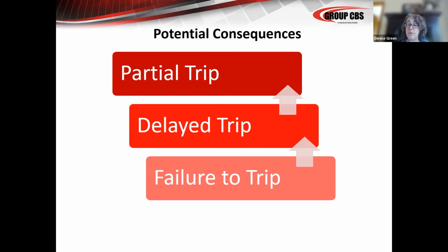What it turned out to be was, all the years that they were having the breakers tested, this was at a utility, so they never shut down the gear. Well, because of this event, the gear had to be shut down to be repaired. And when we got in the back and got the covers off, we found that a connection had not been crimped at time of installation. So all the years of spiking faults on that loose connection on the cable was causing the interrupters to fail. And that caused then the cascade of events.